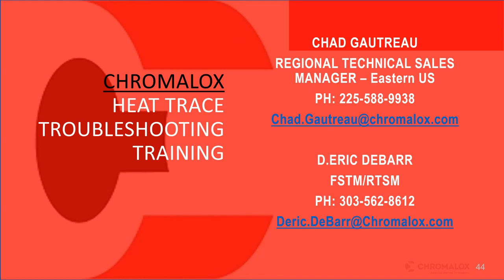A lot of times, if you want to talk about that, like for 50% caustic, we don't want to get above about 100, and most people maintain this stuff around 78 or 80. When you start getting above 100 and 110, 112, it starts to become hyperactive. So in that case, you need something to shut off at a higher temperature limit, or you can also design it such that if you do have a runaway, your cable's not going to overheat that pipe. Okay, very good.